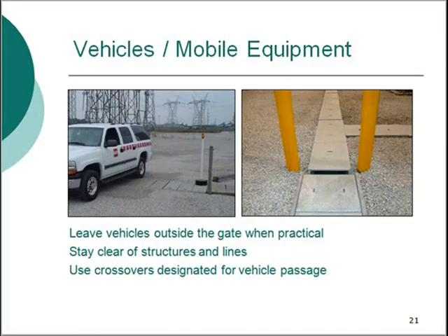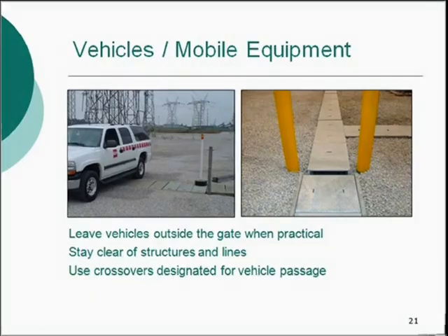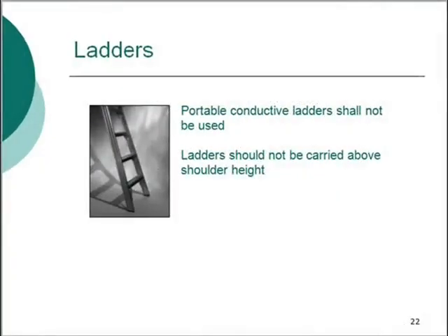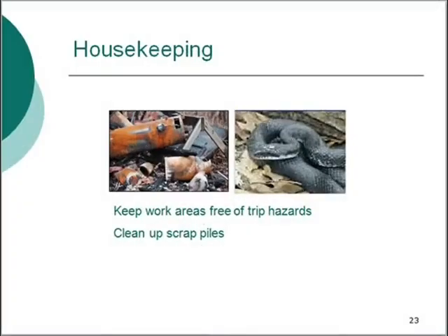A raised antenna or standing on the back of a truck can increase the likelihood of violating minimum approach distance. Only drive across cable tray crossovers designated for vehicle passage. Driving lanes should be clearly marked with stanchions. Tray sections designated for vehicle passage will be covered with steel plates or other materials engineered to support mobile equipment. Portable metal ladders and other portable conductive ladders shall not be used in substations. In addition, ladders should not be carried above shoulder height. Materials should not be stored within the working space of energized lines or equipment. Scrap piles create trip hazards, attract insects, field mice, and snakes, so clean them up.